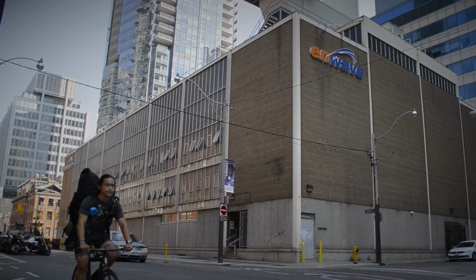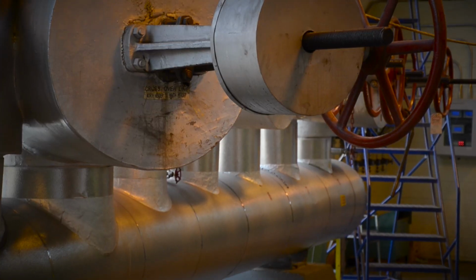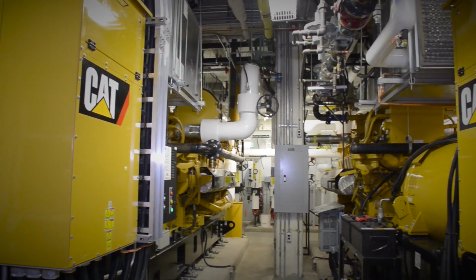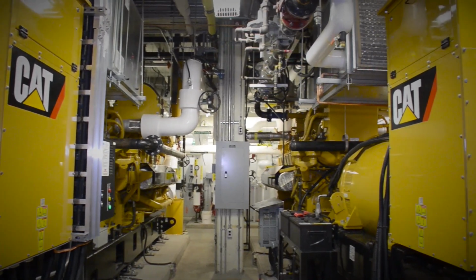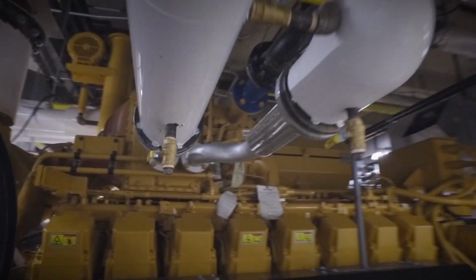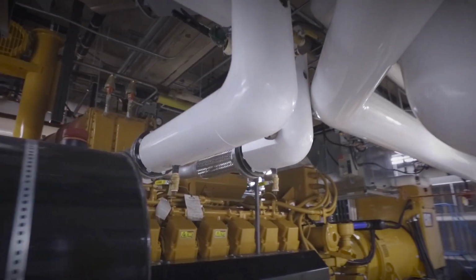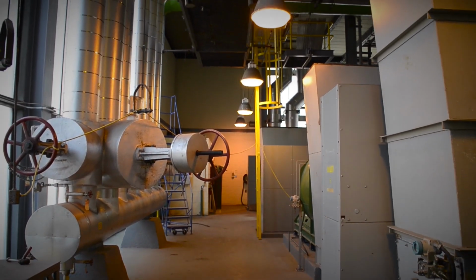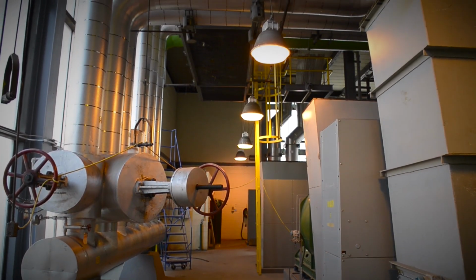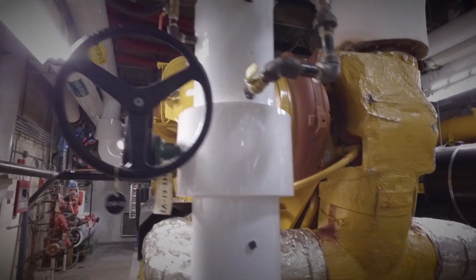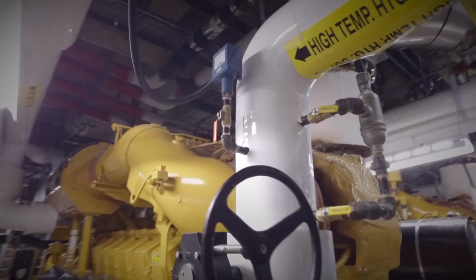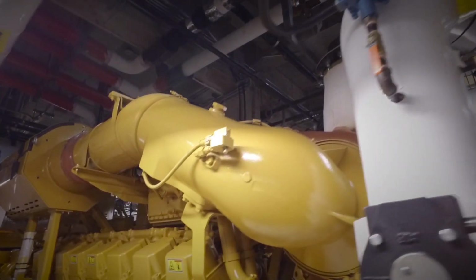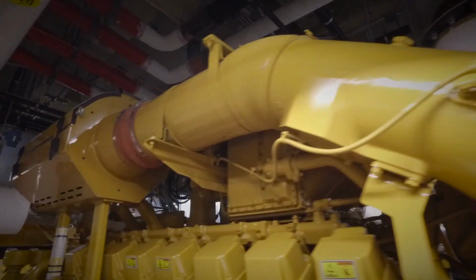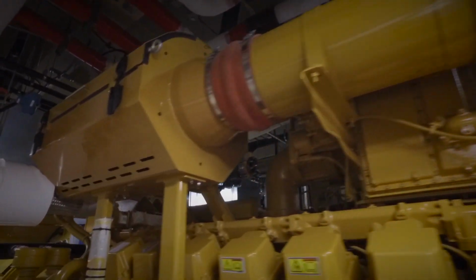The heating system is about 1 million pounds an hour. The plant we're standing in right now is the Pearl Street Energy Center, and we have a very large boiler plant. These engines generate 4 megawatts of electricity, but they also generate low pressure steam into our deaerator systems. The boilers upstairs use water to feed what we call boiler feed water. Rather than having the boilers warm up that water from city water temperature, we're using our engine set to warm up that water before it gets warmed up by the boiler afterwards.